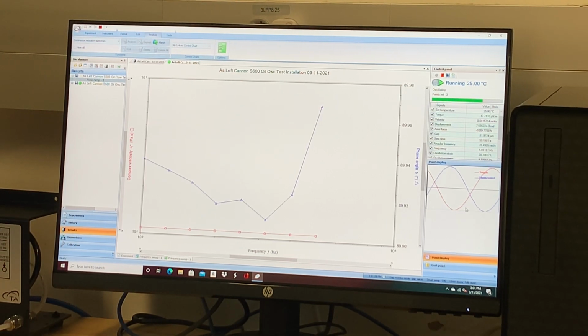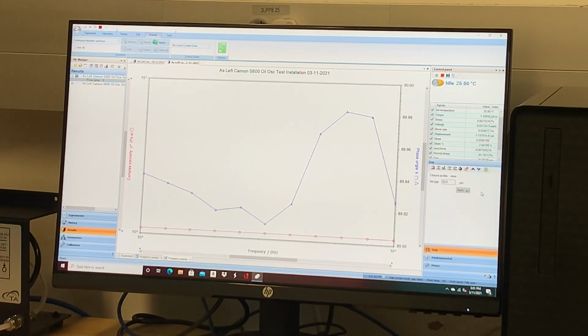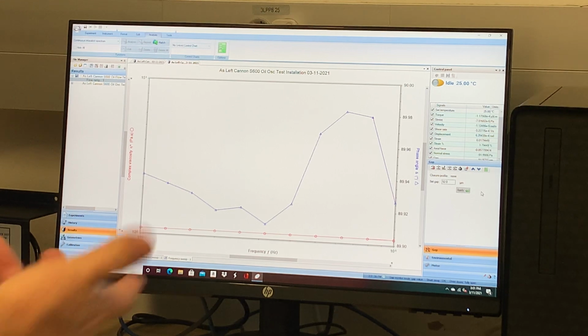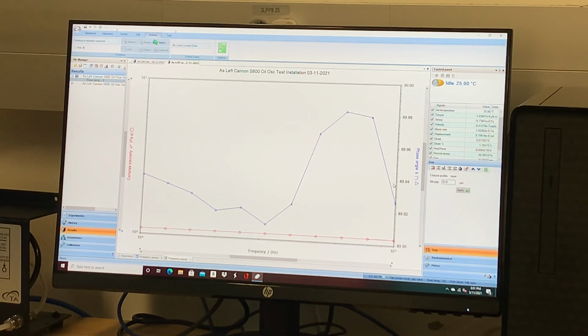This is giving us actual data point display, so it's giving us the torque and the displacement. And because it's a Newtonian fluid, it should be 90 degrees apart, right? If we were running a piece of steel, what would it be? Torque and displacement would be right on top of each other, right? Because there is none. And then all samples are somewhere in between the Newtonian fluid and steel.